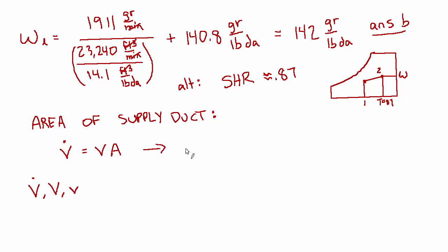If we rearrange this to solve for area, area equals volume flow rate divided by velocity. The volume flow rate is 23,240 cubic feet per minute divided by the velocity, which is 140 feet per minute. The minutes cancel and this feet cancels with one of these feet, so you end up with feet squared. The answer is 166 feet squared, and that's answer C.